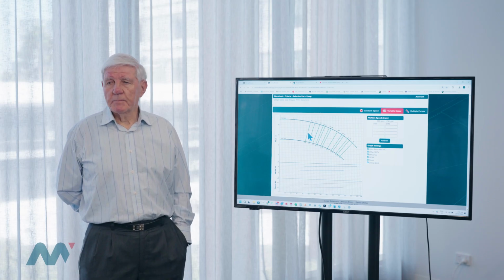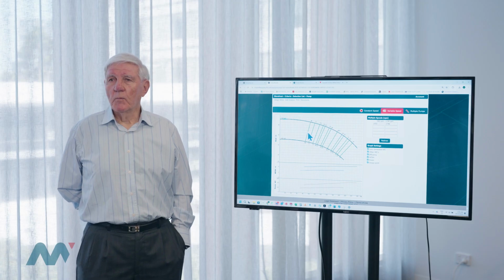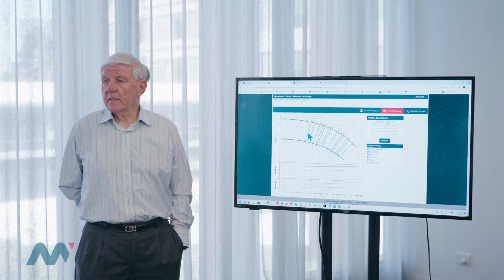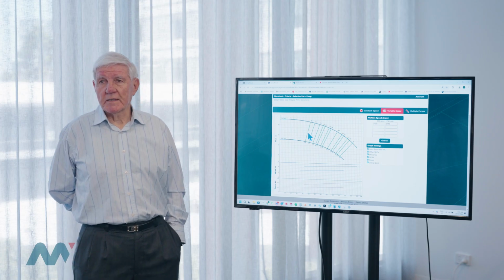What you then have to do is to match the performance of the pump to the load profile. And if you operate 90% of the time at what you might call the normal operating point, and occasionally you have to increase the flow by 10 or even 20%, you could use that frequency change as a way of dealing with that situation. So if you increase the frequency from 50 to 60, there are no impacts on the product. The pump performance should increase by approximately 20% on flow and approximately 44% on head.